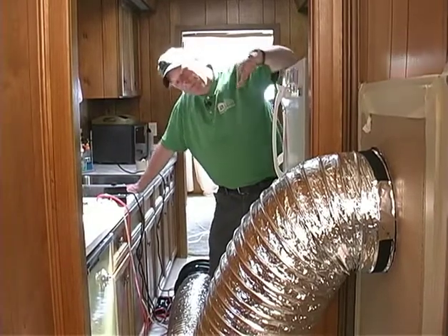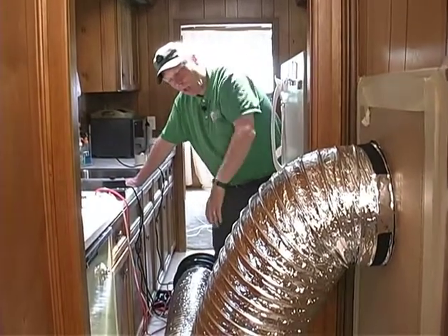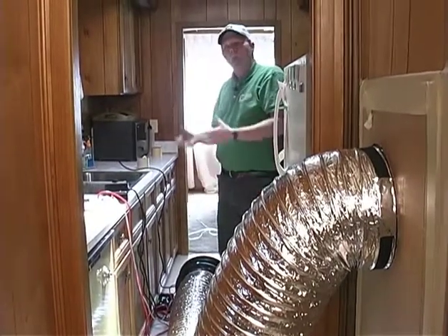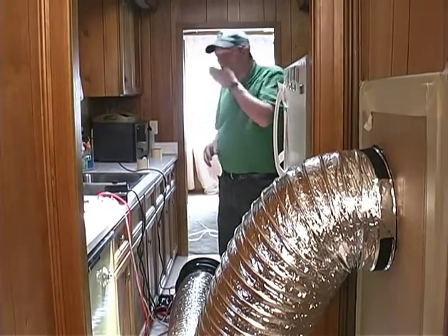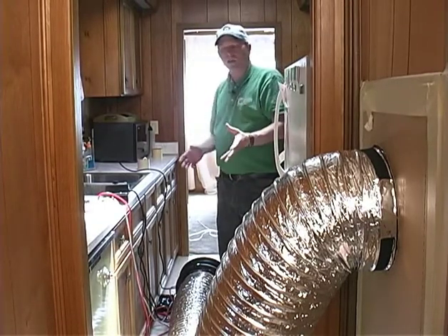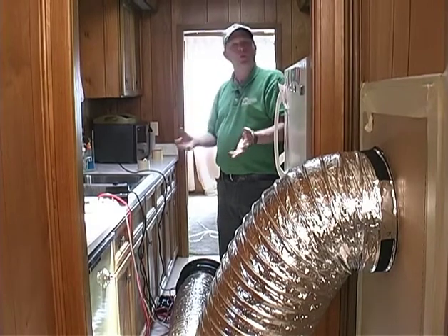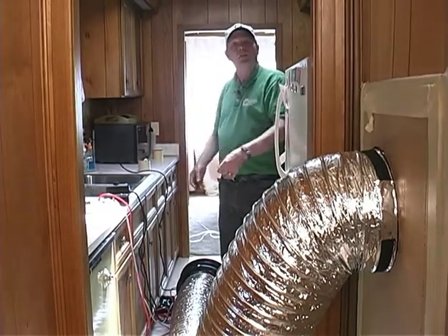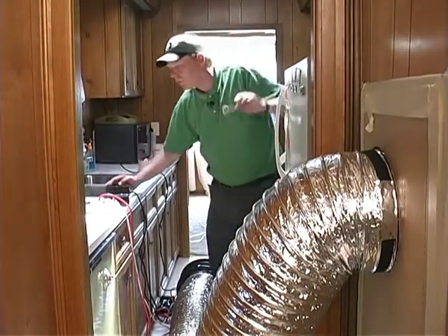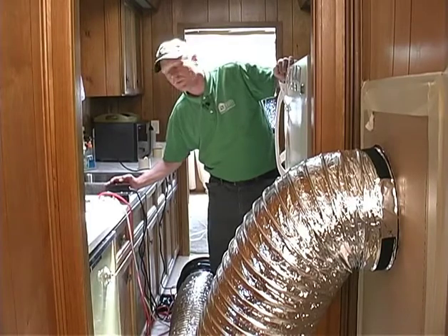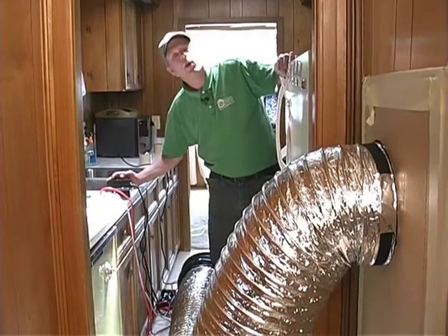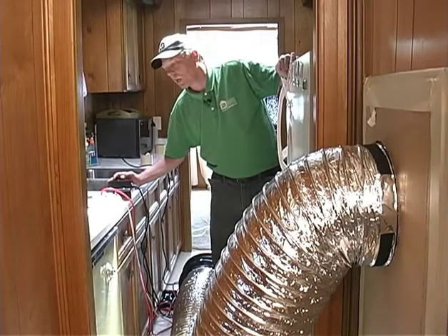And so we've hooked up our duct blaster there, and we are going to pressurize the entire duct system and measure the total duct leakage with this device. It's exactly the same as a blower door test, except we're doing the blower door test on the ducts themselves. So I'm going to go ahead and run it up to 25 Pascal difference here, and we'll get a number, and we'll be able to come up with a hole size for this duct system.